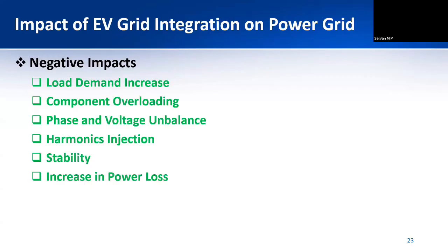Suppose the increase in demand overlaps with the peak demand period—then there will be component overloading. During peak time, say in the evening hours, if charging of electric vehicles happens at the same time, distribution transformers may get overloaded, distribution feeders may get overloaded, substations may get overloaded. So component overloading is another issue to be tackled as the number of electric vehicles increases.